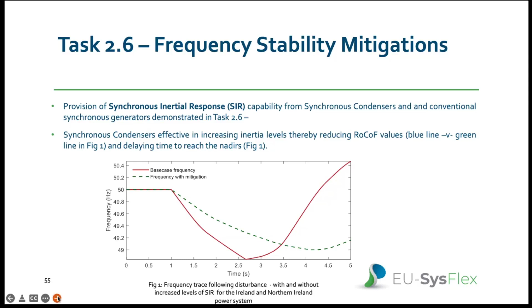Analysis showed that fast frequency response provision benefits frequency stability, especially during times of high SNSP, and has a dual effect: it can increase and delay the frequency nadir, enabling other resources with slower frequency response to contribute. Studies also indicated that frequency response capability in wind can support frequency stability during high SNSP through primary operating reserve.